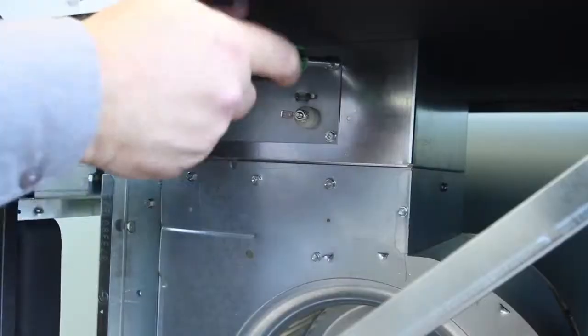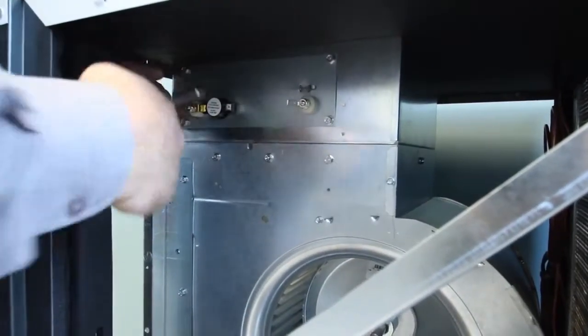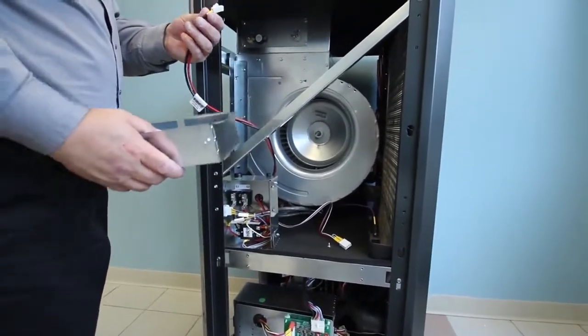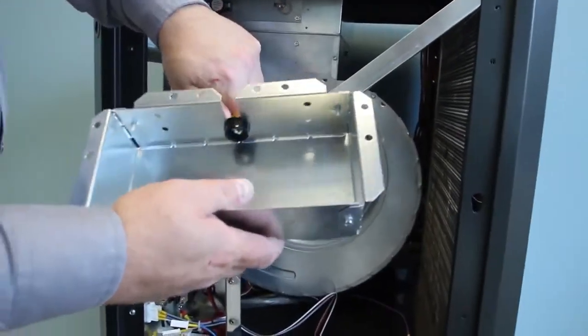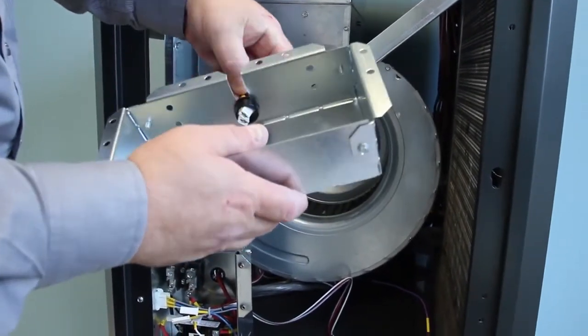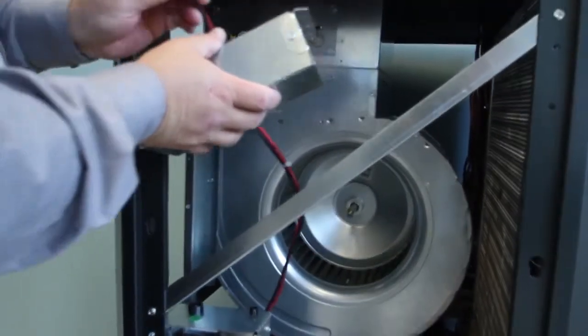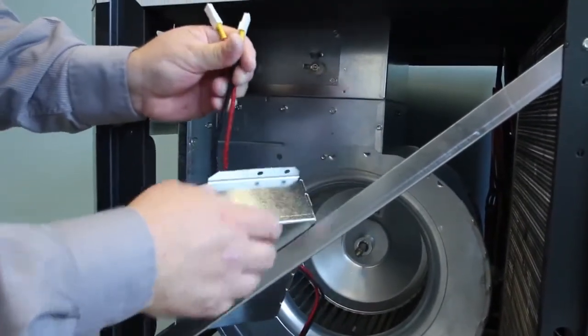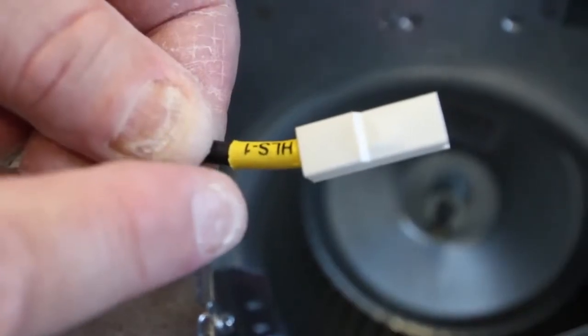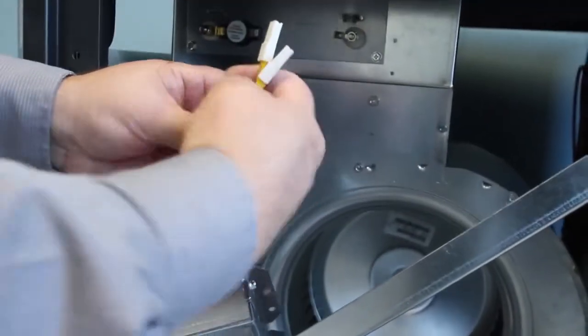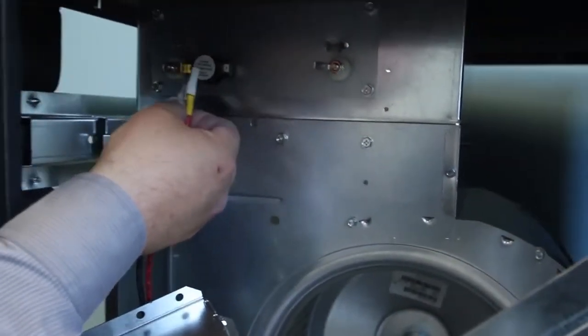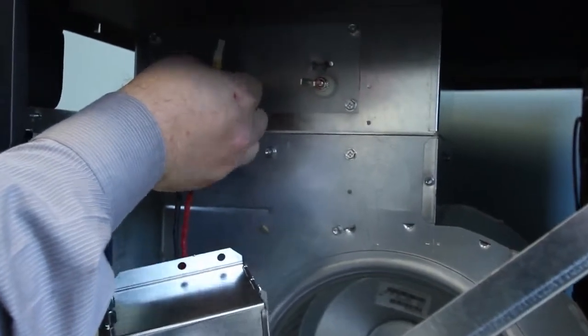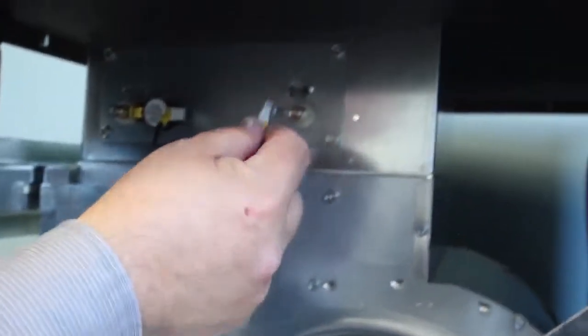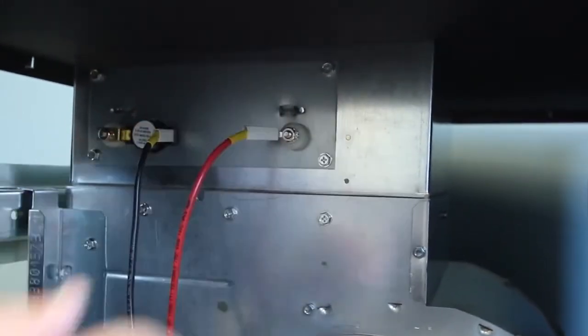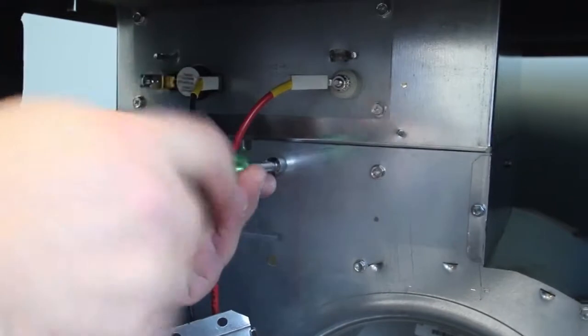Once the heating elements are reinstalled in the new location, the next step is to route all of the wiring from the E-box back to the electric heaters and install in the new position. Connect the wiring harness to the connector on the side of the electrical E-box, and then reconnect the high voltage wiring from the E-box to the heating elements, matching wire number to the terminals as shown in figure 81 on page 23. Once that is complete, you can reinstall the electric heat element covers.